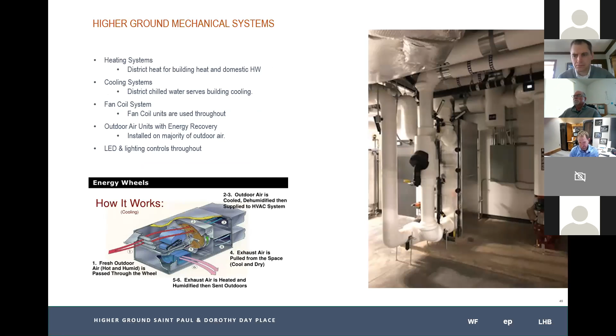Speaking of air handling units, this is one lesson learned after the fact. That green box represents an air handling unit that is on the second floor, and it serves both first and second levels. While it's a great spot for a mechanical room programmatically, it's not as good of a spot in terms of energy performance. It puts our unit quite a ways away from the last room that it serves, upwards of 370 feet. So current energy codes, high performing buildings would call for that unit to be closer to the spaces it serves, in order to conserve fan energy. And so we learned that.